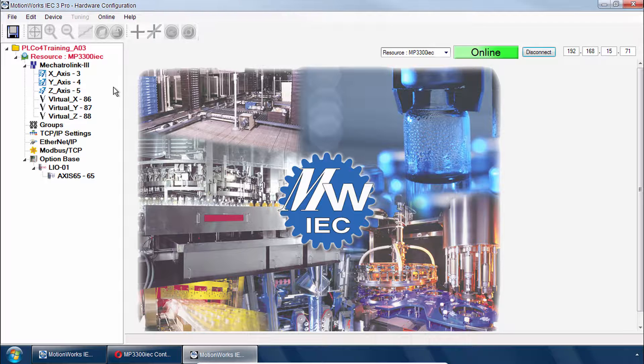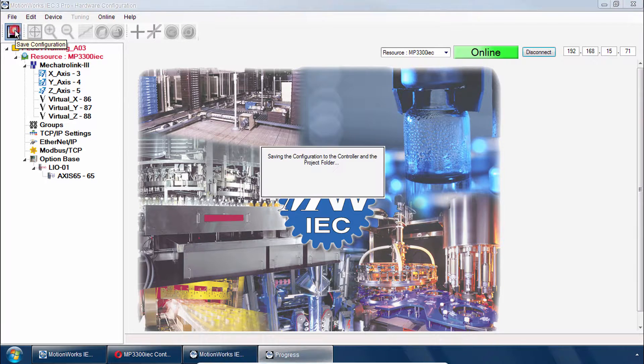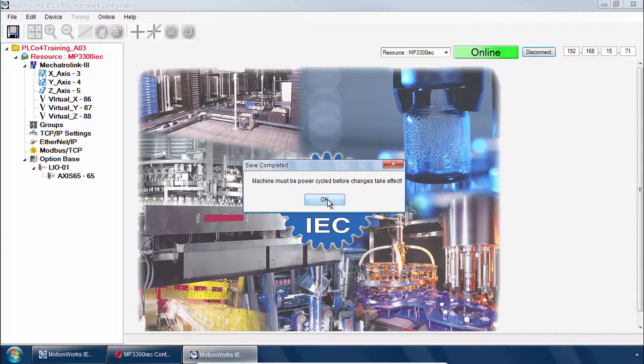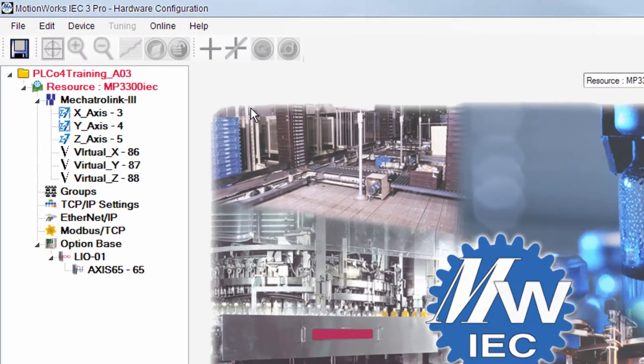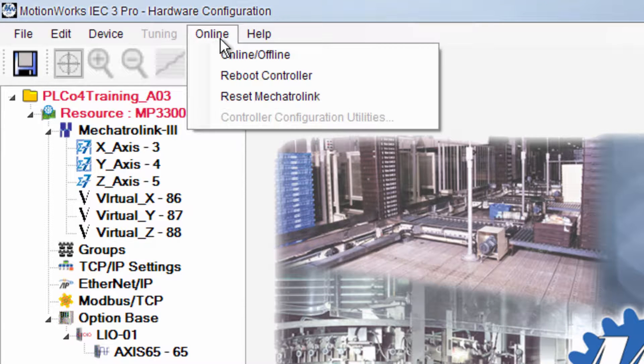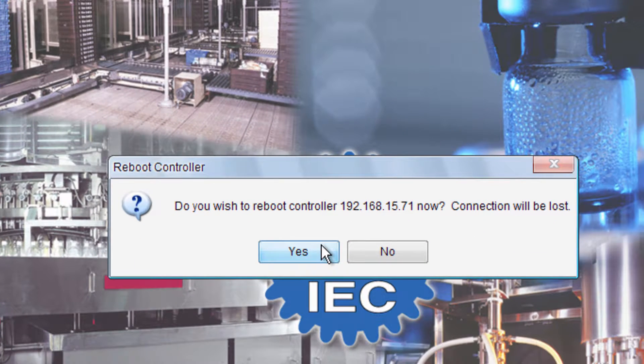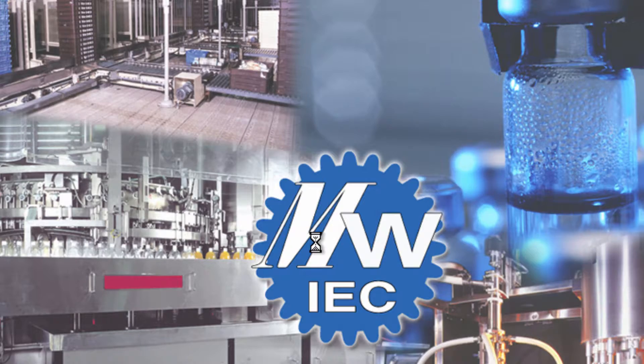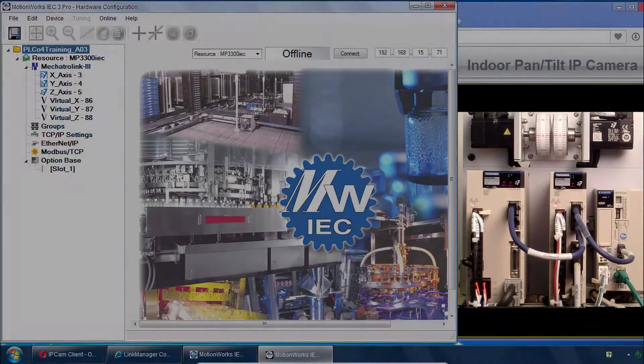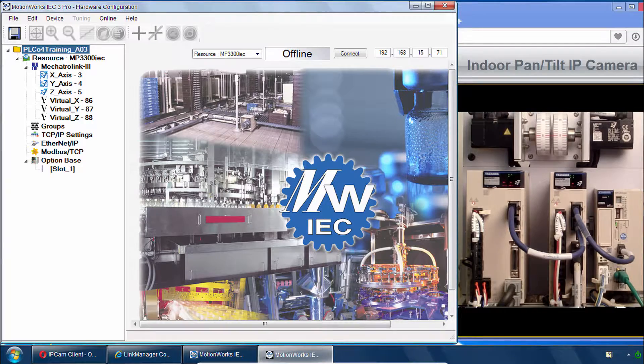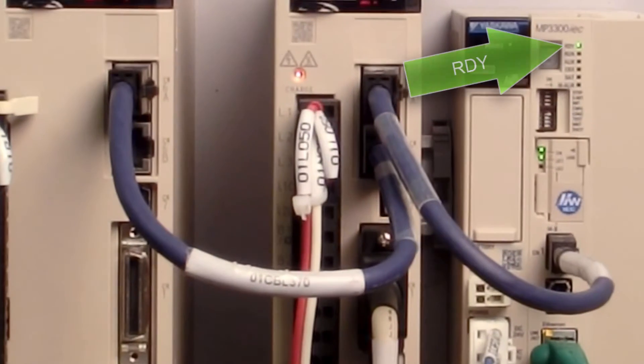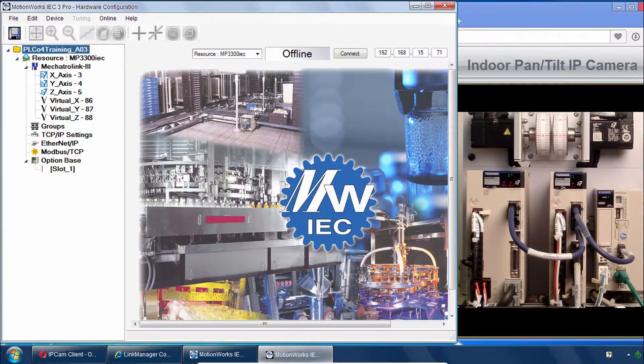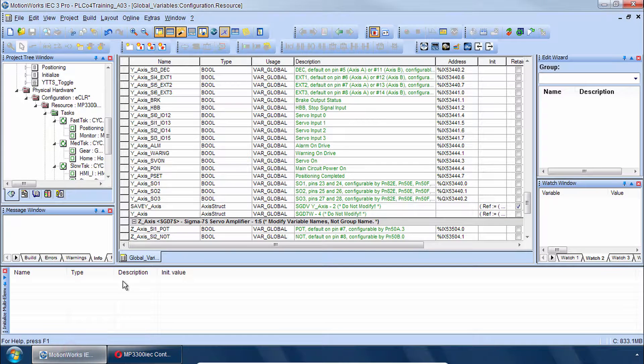Now all we need to do is save while you're online. And when that completes just follow the directions here of cycling power. Just click OK and then you can go to online reboot controller. And wait for that to complete. Now the controller is rebooted and I can even see the ready light is on. So we can close the hardware configuration and go back to MotionWorks IEC.